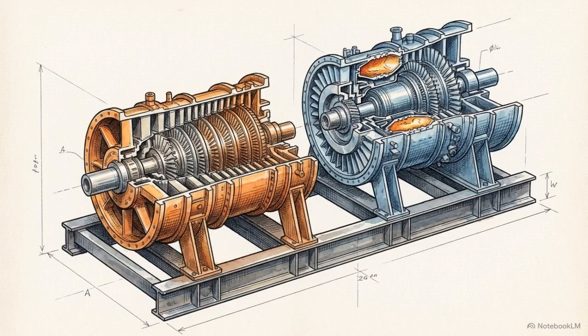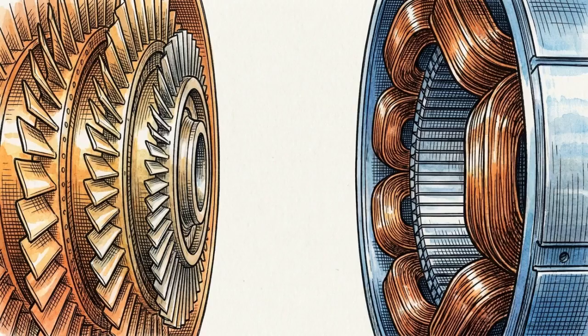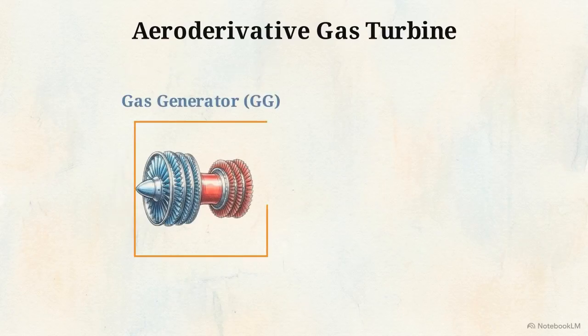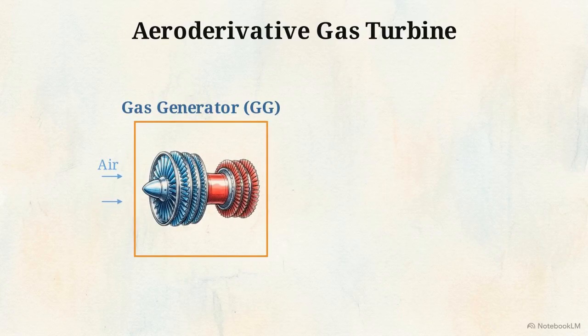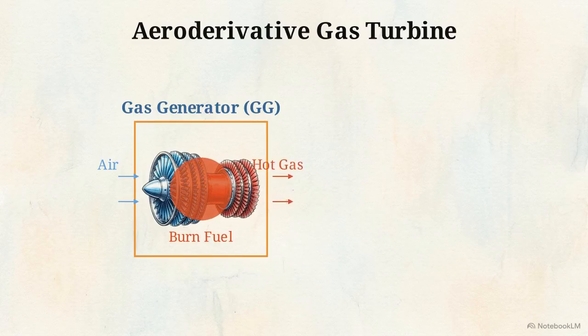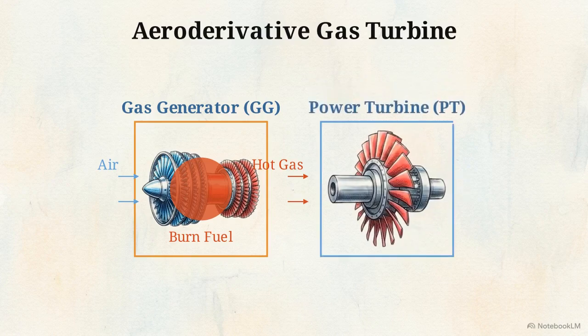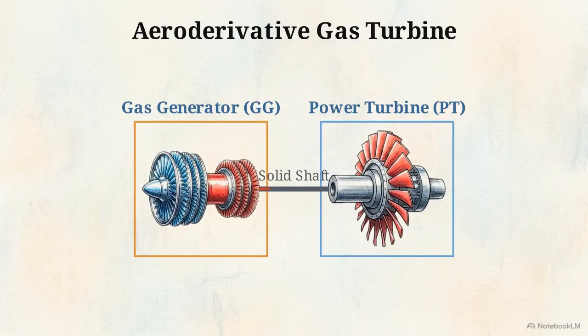There is no physical metal shaft connecting the engine's hot core to the power generator. They are mechanical strangers, even as they work in unison to produce electricity. The engine is built as 2 independent rotating systems. The first is the gas generator. Its singular purpose is to ingest air, burn fuel, and produce a high-velocity stream of hot gas. The second system is the power turbine. It is aerodynamically coupled to the gas generator, meaning the expanding exhaust gas, rather than a solid metal shaft, is what physically spins the turbine blades.